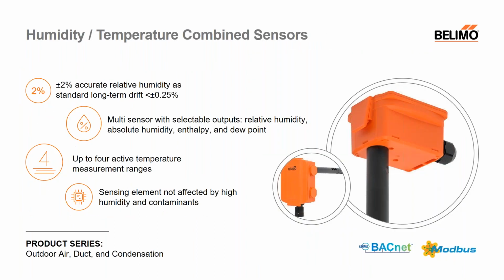So remaining on topic with humidity, I want to go further into the details regarding the units that we provide here at Belimo. Each of our humidity sensors also has an incorporated temperature sensor built into the unit as standard. As I mentioned before, all of our humidity sensors carry an accuracy of ±2% as standard with an extremely low long-term drift value. This low drift value makes our sensors extremely accurate throughout their product lifespan.